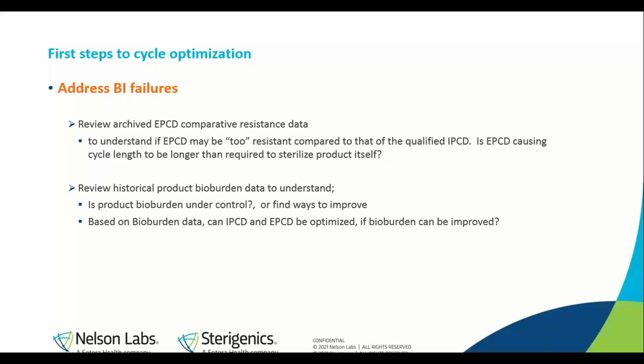Third bullet point is if you were looking to address BI failures. Russ touched base on this one as well, primarily looking to see if, first ask yourself if the EPCD, or the external process challenge device, when it was first developed for your process, may have been too resistant compared to that of the qualified IPCD. And is the external PCD causing the cycling to be longer than what is actually required to sterilize products? For example, in order to sterilize your product from an IPCD perspective, where you're killing the BI in your load, it may require 2 hours of gas exposure, but because your EPCD is much more resistant, you may be requiring 2.5 hours or 3 hours. So that's just something to look at in terms of the EPCD historical data.